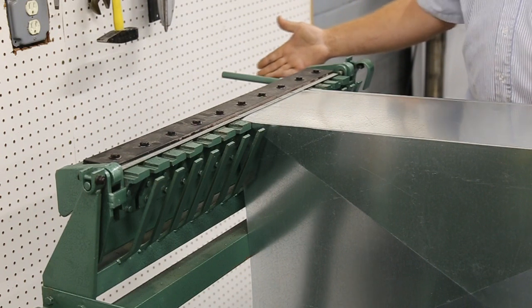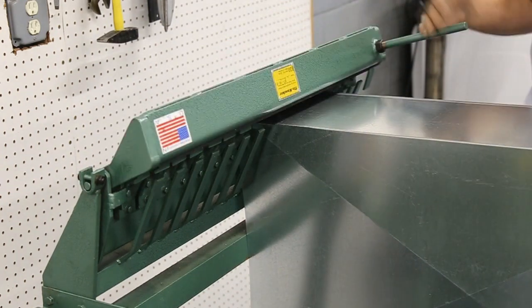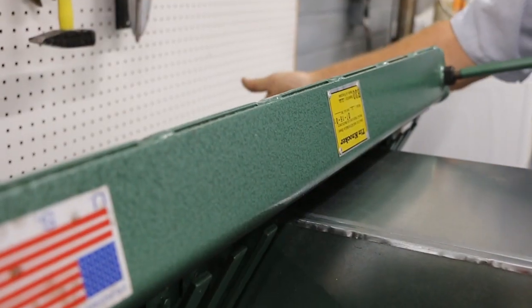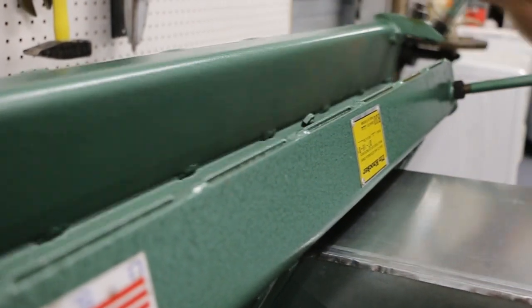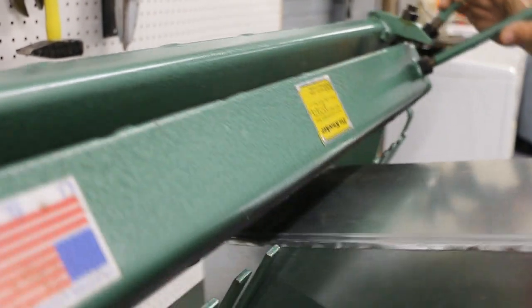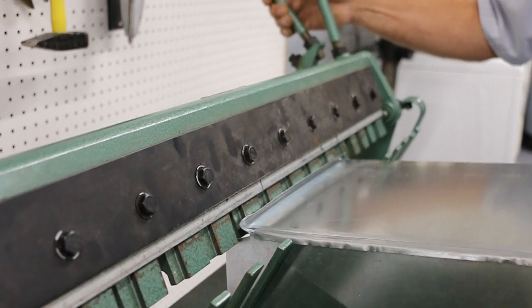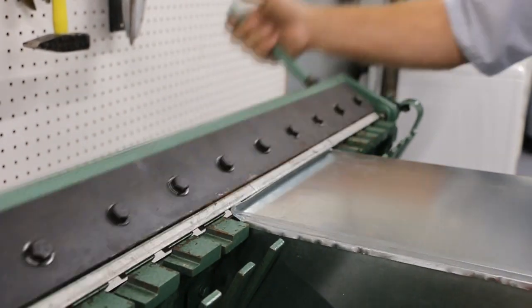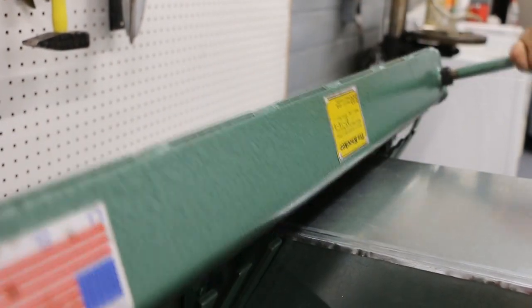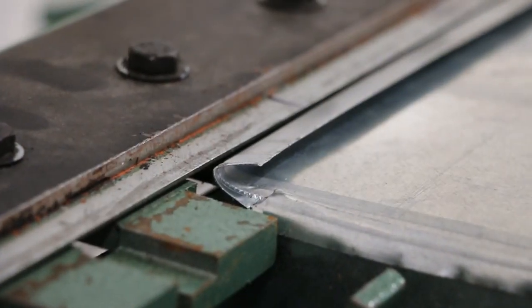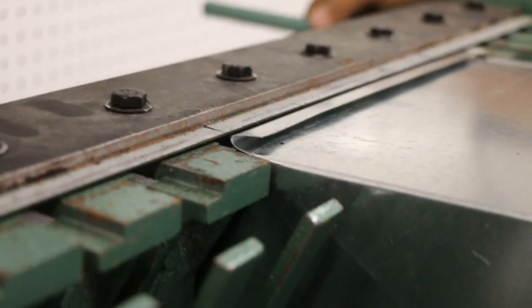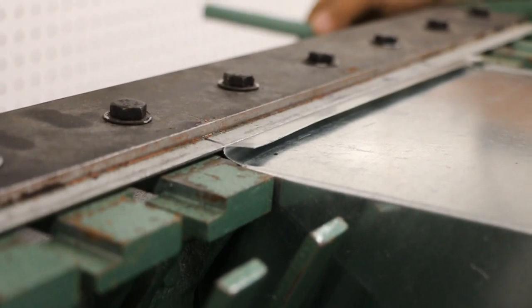To use a cleat bender, you have the top one, which pulls it over part way. There's another handle back here that you hit to release, push it forward and it drops back out. Then you bring that top one back over. It bends your half-inch, but it doesn't smash it over all the way, because if it's smashed all the way, you can't get your drive cleat on.